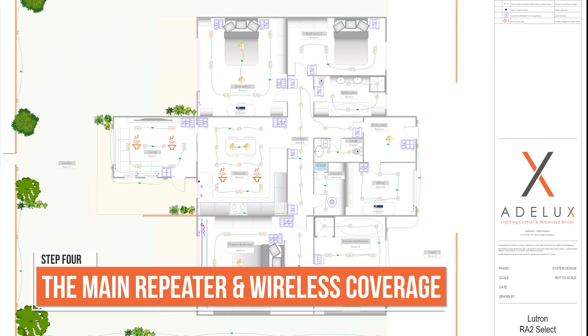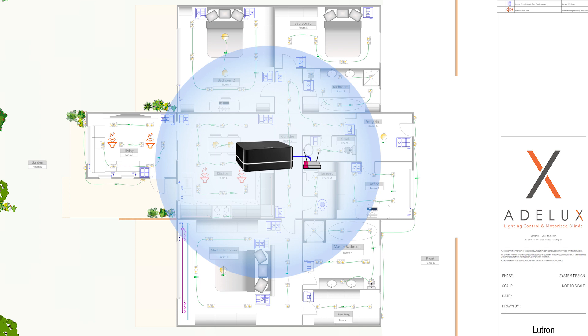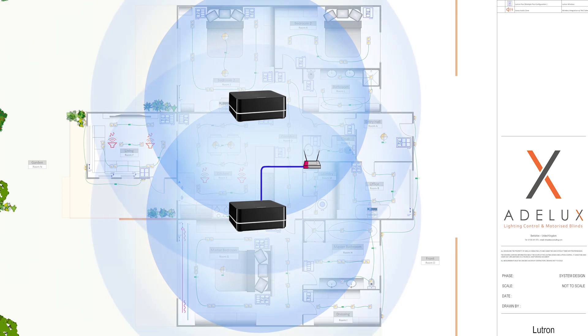Now, to program all this equipment and allow the client to control and monitor the system using the Lutron RA2 Select app, we need a main repeater. The repeater needs to be connected to the internet router of the house. All the RA2 Select devices need to be within a 9-meter radius from it, which here covers most of my Lutron equipment, but may appear a bit short for some of them. The Lutron Clear Connect wireless communication is very, very good, and I feel confident I can reach every device. However, I will let the client know that we may need to add an auxiliary repeater in case we need to expand the coverage — and this can be added later, so it's not really a big deal.